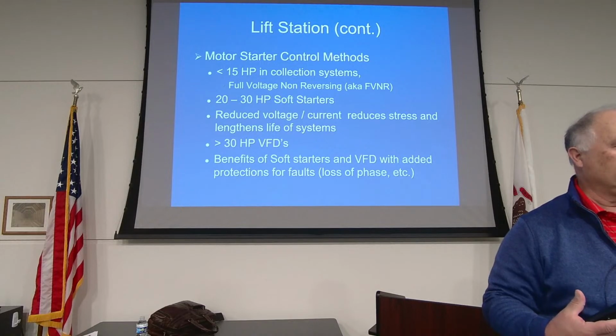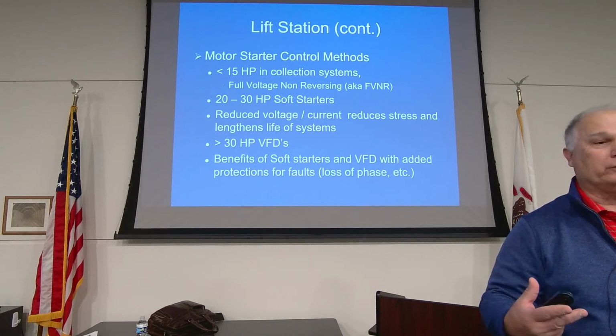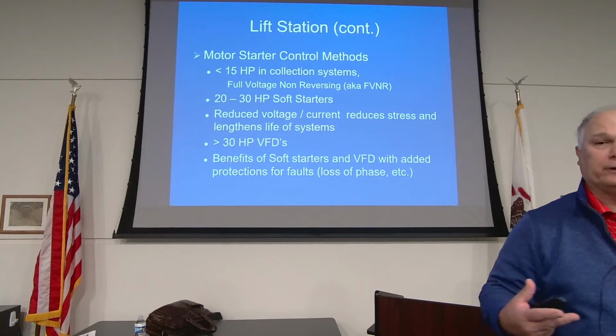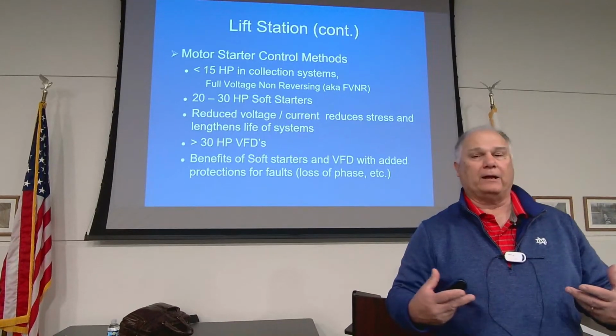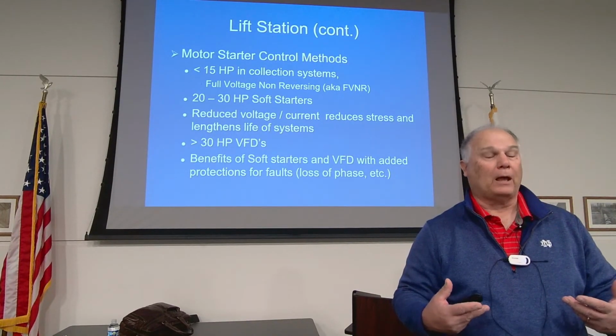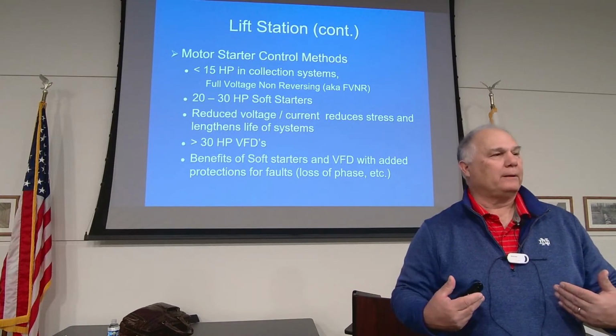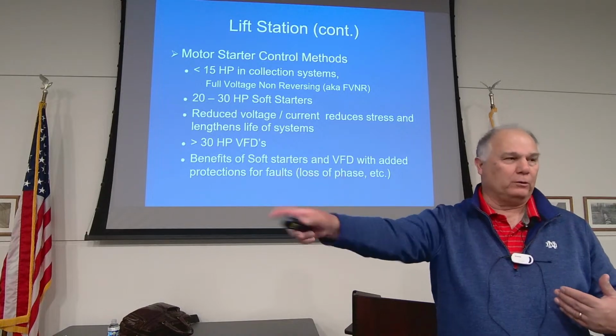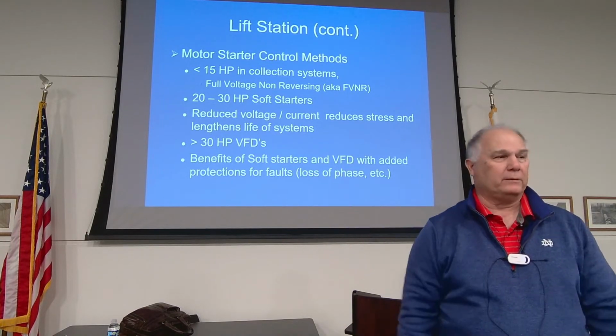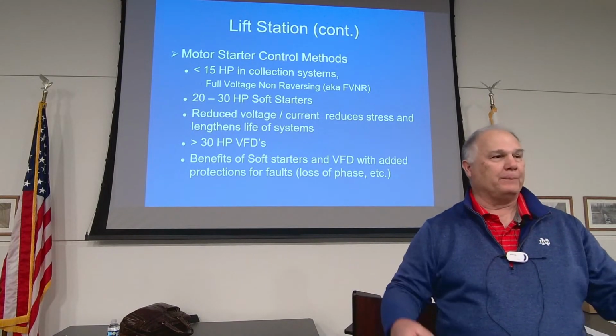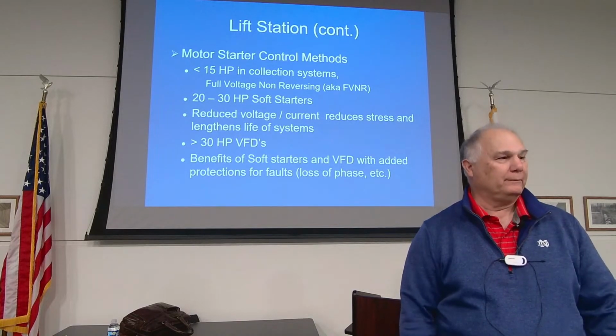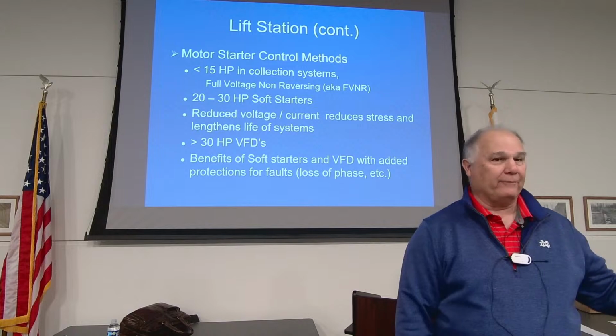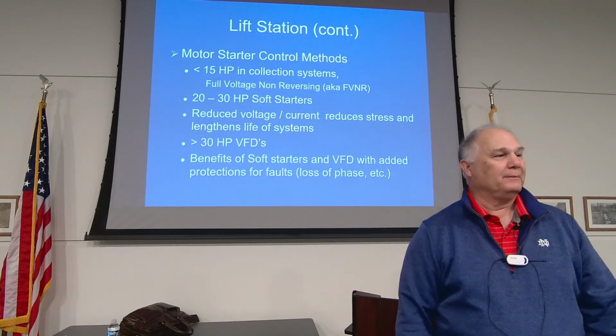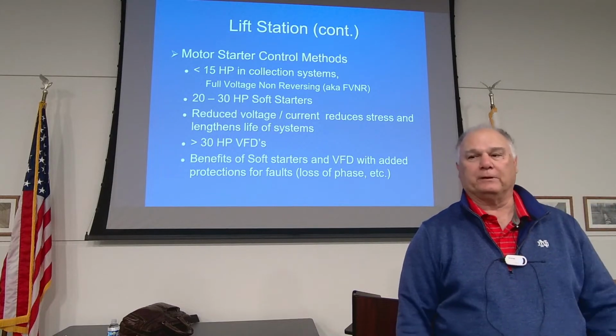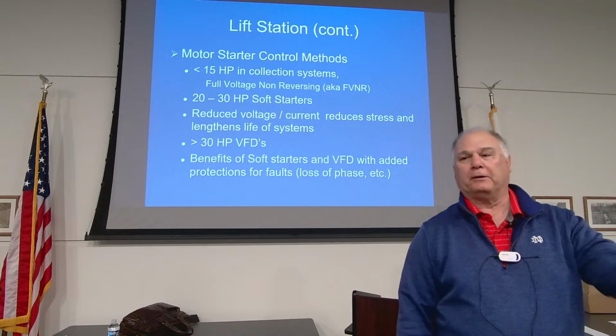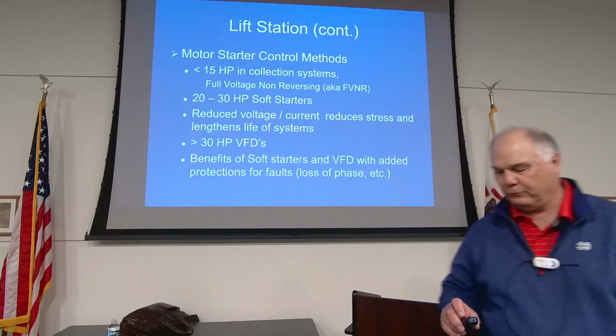Same thing. Therefore, what happens is there was a station in northern Missouri, a 50 horsepower, 230 volt 3-phase motor, which they had on an across the line start. Wasn't our decision. So they put it online, and they had a line coming down feeding about half a dozen homes on this one street. Every time that pump station turned on, every house down that street, you'd see the power go, all the lights would dim. Every time. After a few years, somebody complained and said, all right, we're going to change it. So they brought a separate line in, they did some other things, because refrigerators were starting to burn up, air conditioners in the summer, all that other kind of stuff. We're challenging.